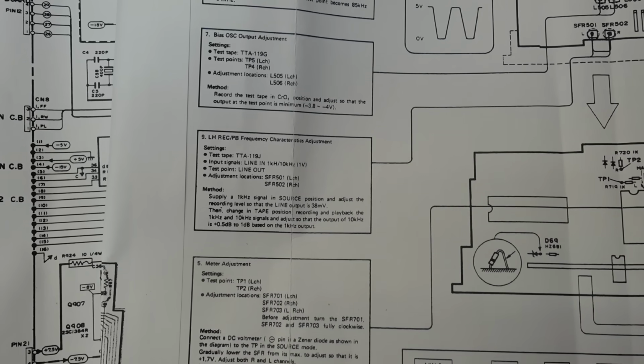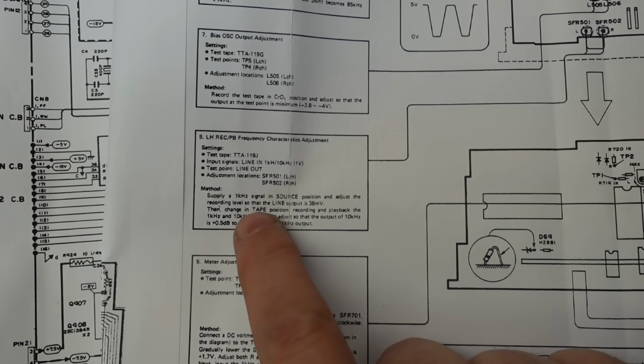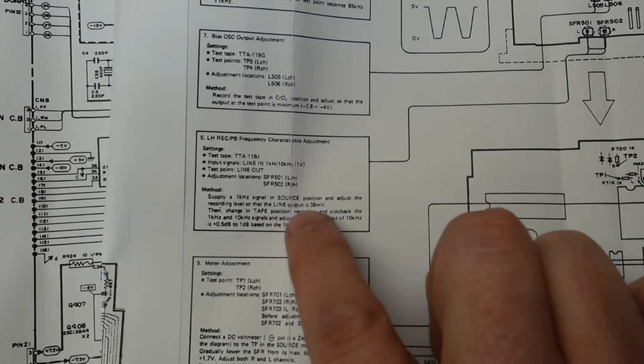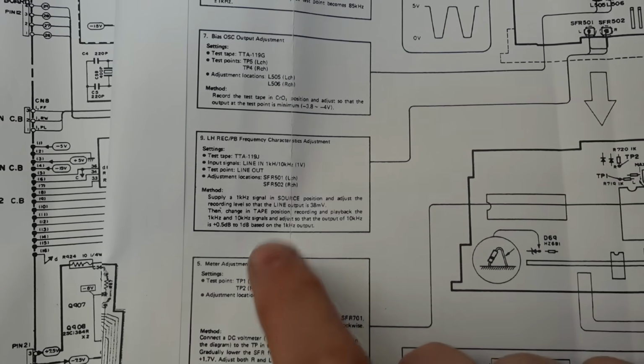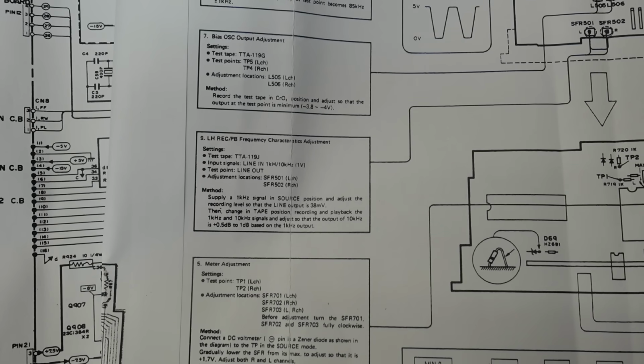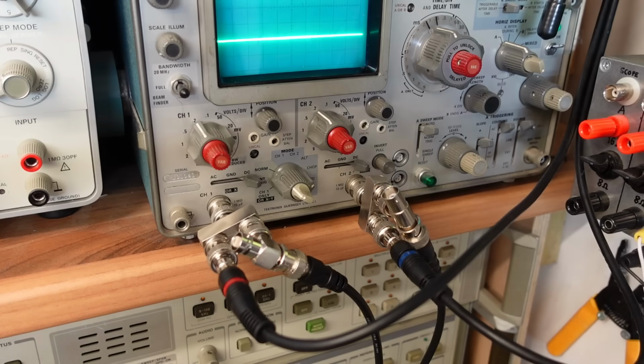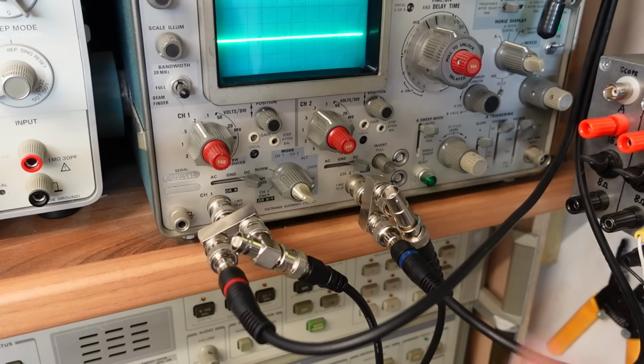The next stage is to adjust the frequency characteristics. We've got to supply a 1 kHz source, adjust it to 38 millivolts on the line output, then compare 1 kHz and 10 kHz signals and make sure they're slightly different. I've got the line output connected to this old scope and it doesn't measure anything.